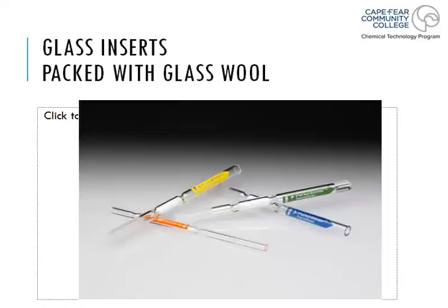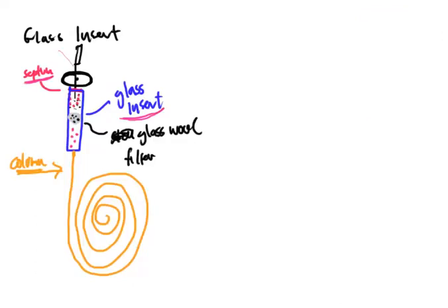So these things are very fragile, but they're not terribly expensive. That's why we typically trade them out every time we change out a rubber septum, just to keep our system clean and to make sure there's no trashy contamination that comes from using a dirty glass insert. What will happen, I keep saying trashy and contamination, is that over time, these materials could become loose. And if those materials come loose, they could start to trickle inside of the column, little by little. And then on the chromatogram itself, over here to the side, you would see your traditional peaks that you would always see in a gas chromatogram.